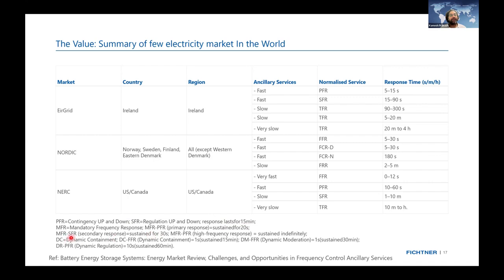Similarly, for mandatory frequency response, MFR, we have a mandatory primary response sustained for 20 seconds only. For the secondary response, it will sustain for 30 seconds, just like our primary and then secondary response, so obviously it will be a little more than the primary. Then there is dynamic moderation fast frequency response. Dynamic moderation involves firming and frequency response at the same time, with a huge battery. So you will participate in FFR, fast frequency, as well as automatic and manual frequency response. We call them FFR, AFFR and MFFR. Your system will be ready to dispatch for all three. Dynamic moderation sustains up to half an hour.